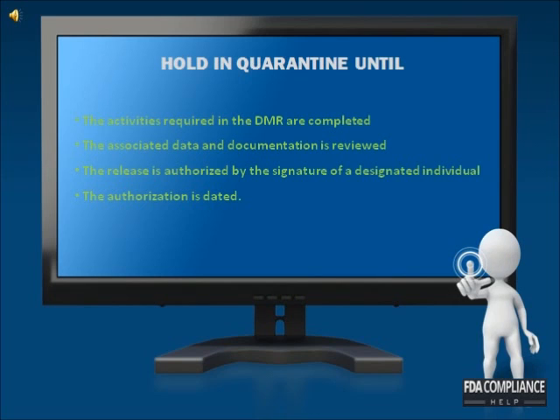The facility is to establish and maintain procedures for final device acceptance to ensure that each production run, lot, or batch of devices meets acceptance criteria. The devices shall be held in quarantine or otherwise adequately controlled until released. The devices shall not be released for distribution until the activities required in the DMR are completed, the associated data and documentation is reviewed, the release is authorized by the signature of a designated individual, and the authorization is dated.